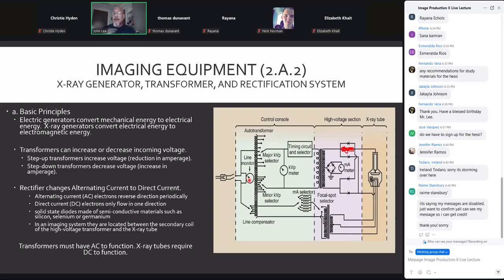Older systems have a line monitor that allows us to know how much voltage is coming into the system. Also, how much amperage is coming into the system. It used to be necessary because we would have to adjust, because the electricity flowing through the city grid fluctuates from time to time. If the voltage is off just a little bit coming into the machine, it's going to affect the energy of the X-rays that we produce. So we would have to check it before every exposure to see exactly what voltage is coming into the system. If it was low or high, we could use a line compensator to manually adjust so that we get the correct amount of voltage in the system.